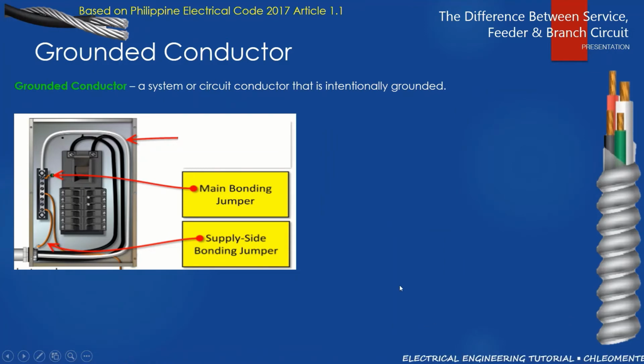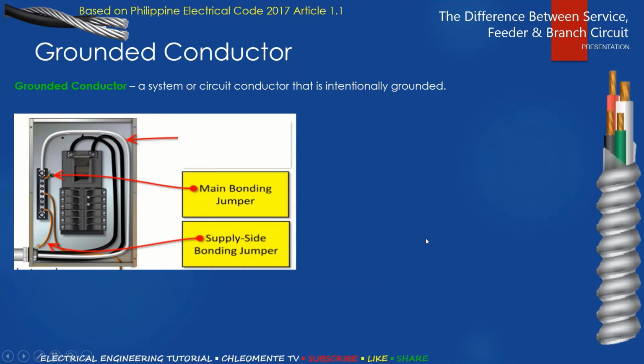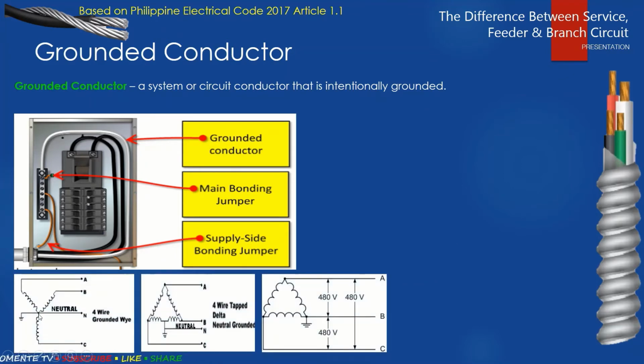So, grounded conductor naman. So, ito yung mga circuit conductor that is intentionally grounded. So, lahat ng iyong conductor sa system mo na intentional mong i-ground, tawag dyan, grounded conductor. So, just in the case of secondary side ng transformer na Y, and you have a neutral conductor. Kung may mga single phase ka nakakabit between phase A and neutral, like lightings and outlet, so normally ginagrounded natin yan. So ngayon, kapag naglagay ka ng ground between the neutral and the main ground bar, or i-ground mo yan, so yung neutral mo ngayon ay matatawag na grounded conductor.